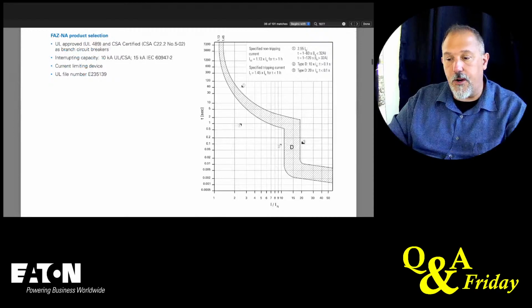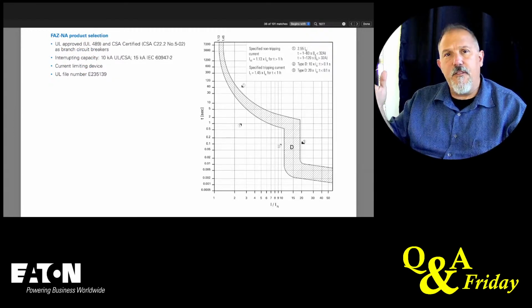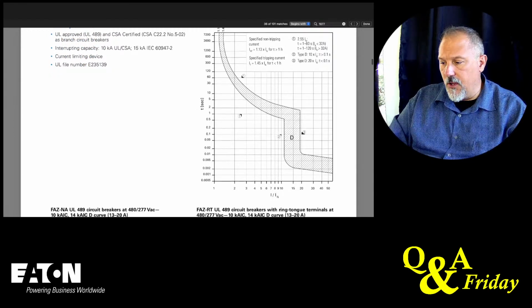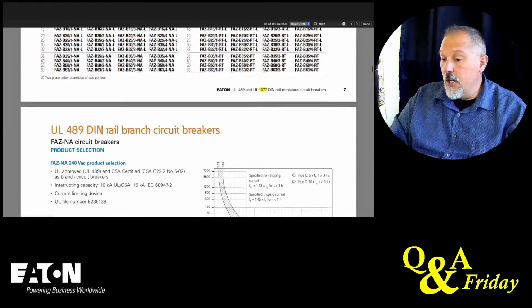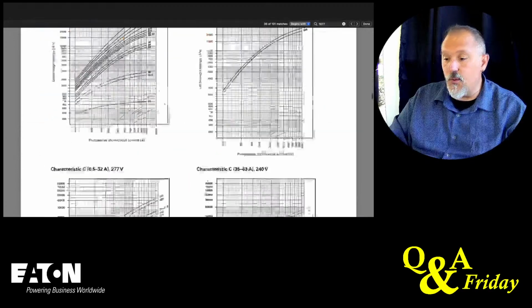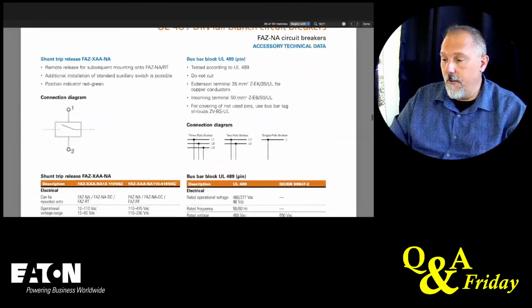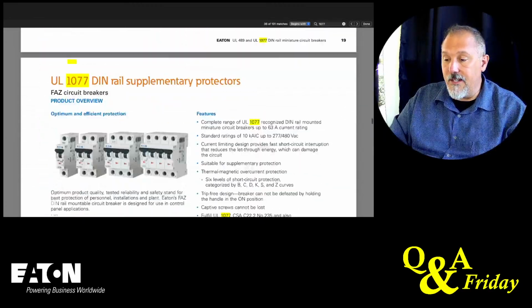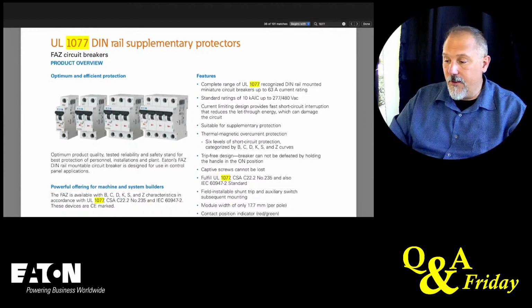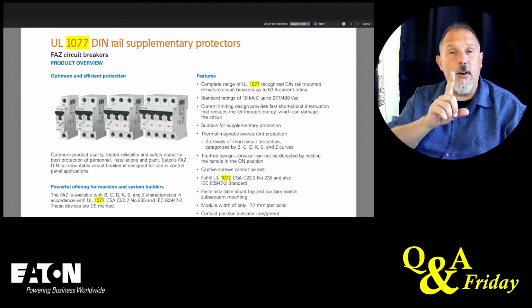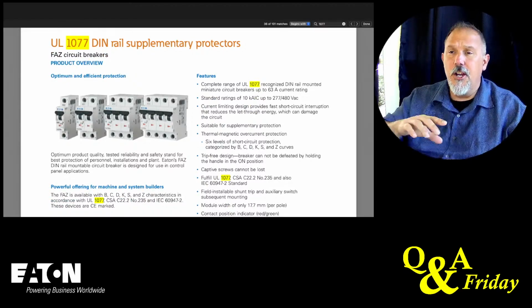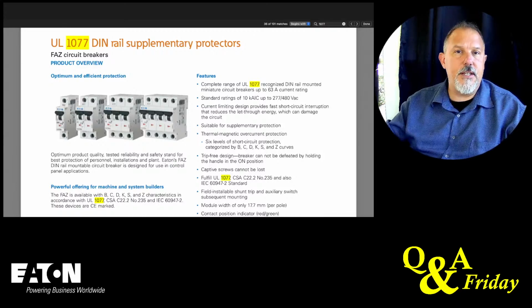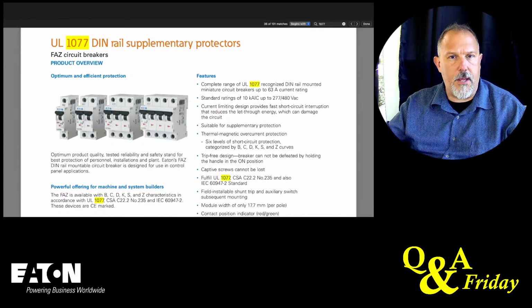Okay, so we're going to scroll down and take a look. Now, these are all the trip curves for 489 devices. You'll notice we have the long time pickup, and then we have an instantaneous region down in here, right? So now we're going to scroll down till we get to 1077 DIN rail supplementary. So these are 1077 devices. And where are you going to see a 1077 device? You're going to see it in HVAC equipment, industrial control panels.